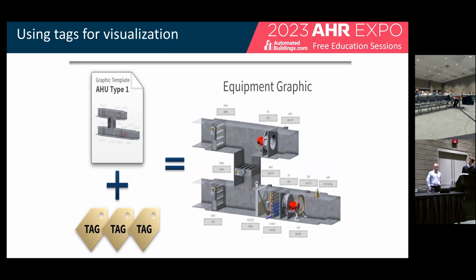Finally, one of the biggest pain points we all have, both as end users looking at graphics and realizing the point is really not connected to the right sensor, is all the labor that goes into the user experience. Here's an example of an equipment graphic - every one of these labels and widgets is tied back to a real point in the system. Back in the day, doing BACnet or LonWorks, I'm literally dragging and dropping a point as an application engineer, and the end user is looking at a screen of all those relationships that were handmade to this graphic. So what if we took that same concept of tags and made all the linking back to the user experience dynamic?